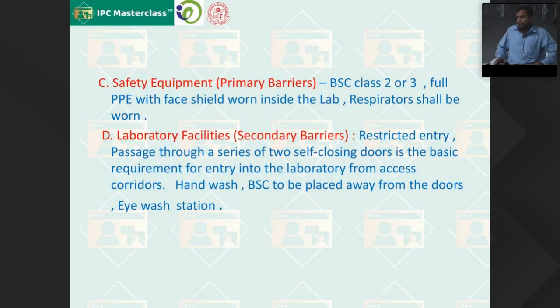So for BSL3, we are required to have double door entries and hand wash, and the biosafety cabinet to be placed away from the doors. Whenever we are placing any biosafety cabinet in the laboratory, make sure that it should not be in a place where the highest air current flow or changes of airflow are there. It should not be near doors. It should not be near windows where you have a high flow of air, and that will disrupt the air flow directions in the biosafety cabinet. So always make sure that it is away from the doors and the windows, and the eye wash stations have to be there.